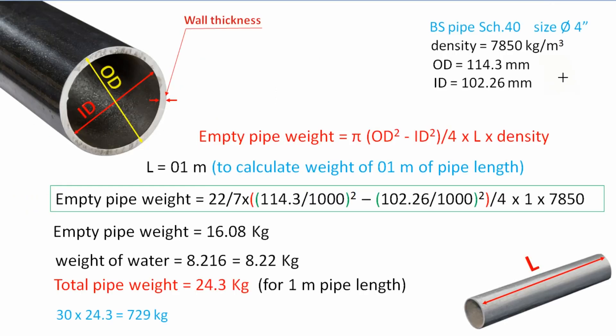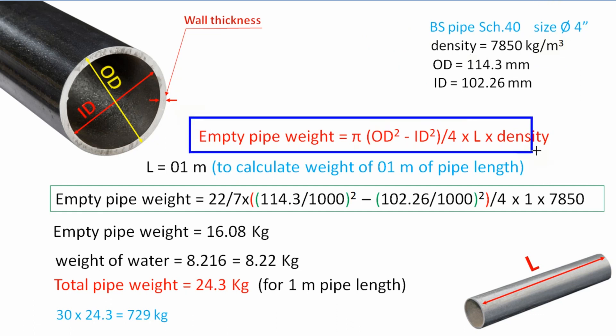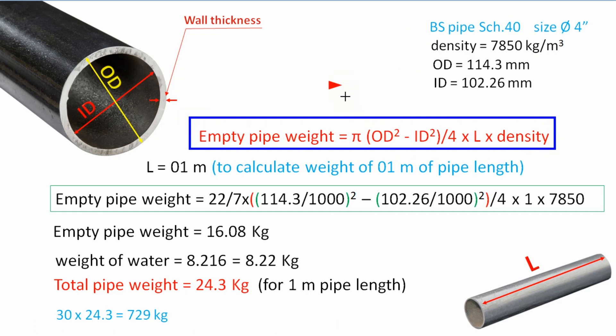Now we will calculate the empty pipe weight. The pipe outside diameter we already selected and inside diameter we have also calculated. The density for carbon steel is equal to 7850 kg/m³. To calculate the empty pipe weight, we use this formula: empty pipe weight equal to pi × (outside diameter² minus inside diameter²) / 4 × pipe length × pipe density.